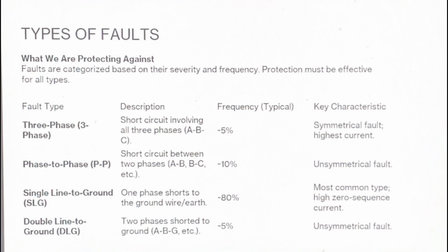The vast majority of issues, approximately 80%, are single line to ground, SLG, faults. This is usually environmental, an insulator flashing over due to moisture, a lightning strike, or a wire contacting the ground. Because SLG faults are so common, the design of any protection scheme must be focused on quickly and reliably detecting and isolating ground faults. This requires special zero sequence current measurements.